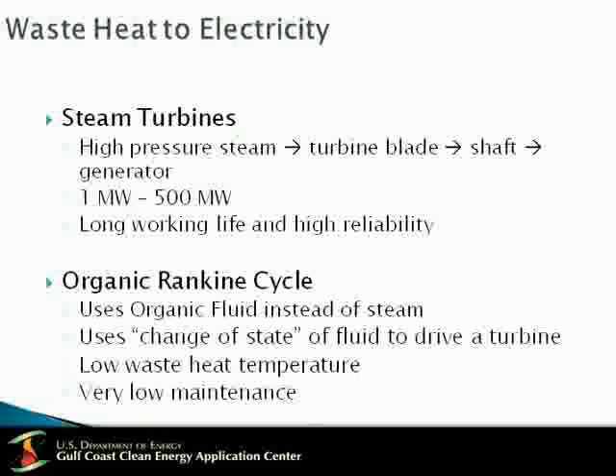Waste heat can also be converted to additional electricity, most commonly through steam turbines and organic Rankine cycles. In steam turbines, you have high pressure steam that rotates the turbine blade and that produces electricity. You have a size range of 1 megawatt to about 500 megawatts. It's a long working life and very high reliability system.